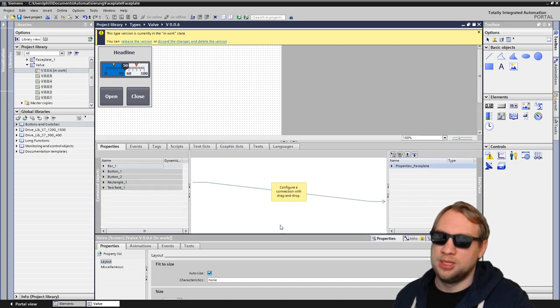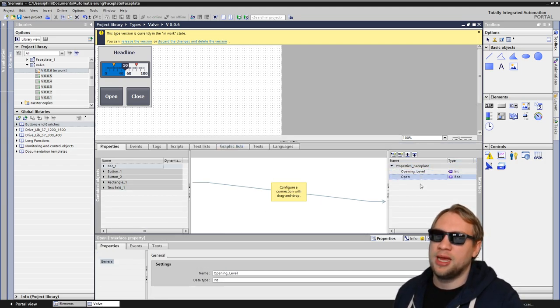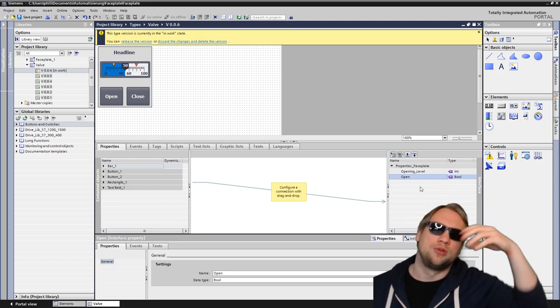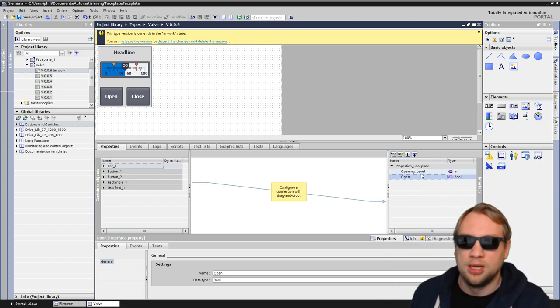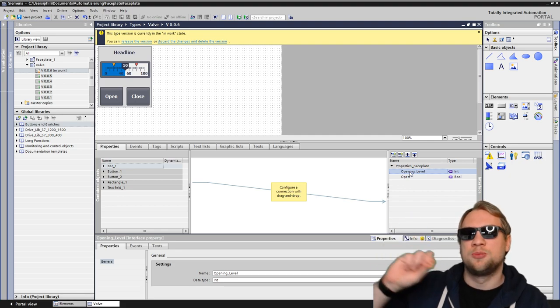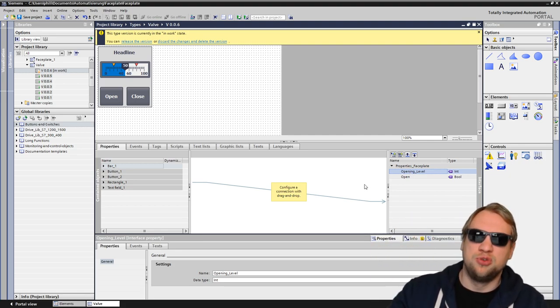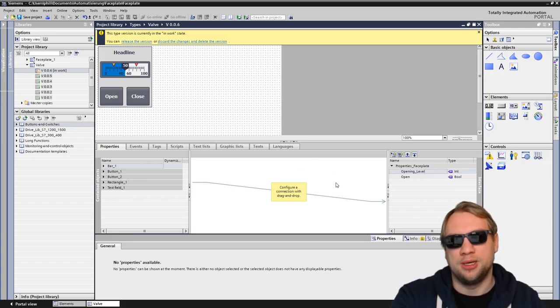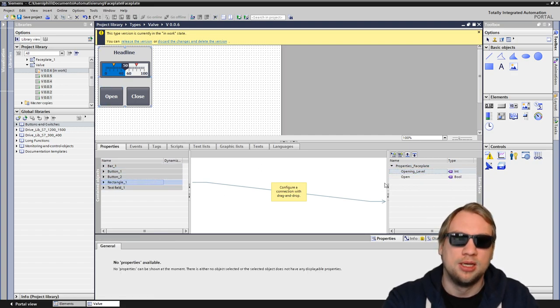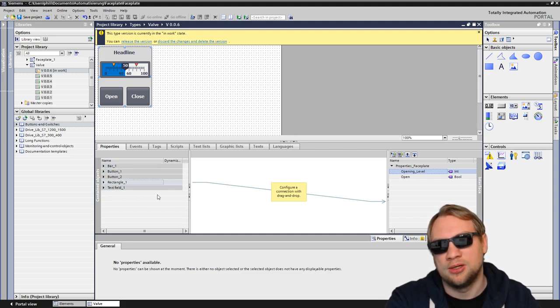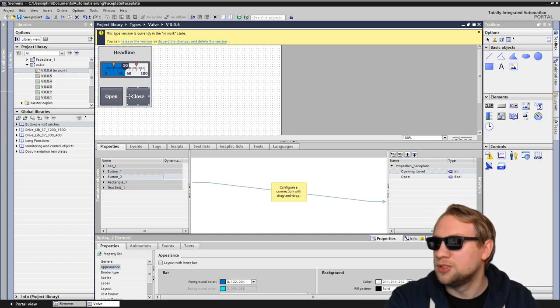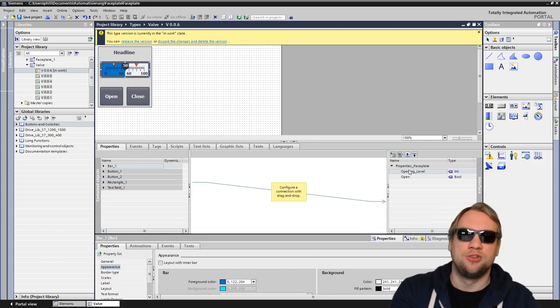Now we are looking at this window here in the middle. On the right side I have my faceplate properties - this is my interface here. Those two are my interface. They can be controlled somehow from the outside, looking at variables from the outside. Now this opening level should come from the slider, and that's what we already set on the outside. But what does it do inside? There is no connection here in between - we have to create an in-between. This here is on the outside, and this here on the left side is on the inside. So we need to decide where this opening level goes on my inside. Of course, it should go to my bar.